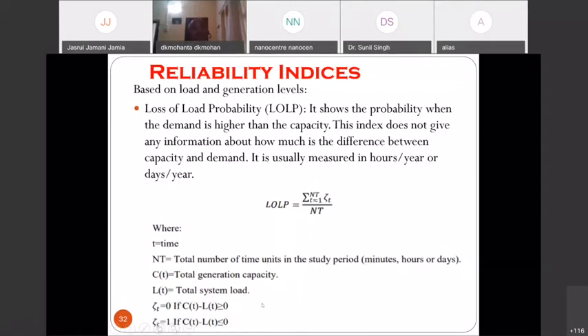So this zeta t was 1 for 4 times. Each zeta t is 0 if CT is greater than LT, satisfying the condition, so it's 0, 0, 0, but where it is not satisfying it is 1. Let us say it was 1 for 4 times out of 100, so 4 by 100, giving 0.04 as the LOLP in that case.